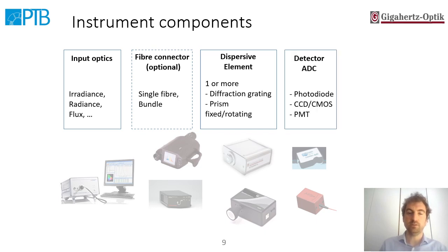Next is the detector, which could be a CCD or CMOS array. And finally, we have the software. Important here is that the software is part of your measurement system. So if you have a software update, you have to check that your software delivers the same results again.